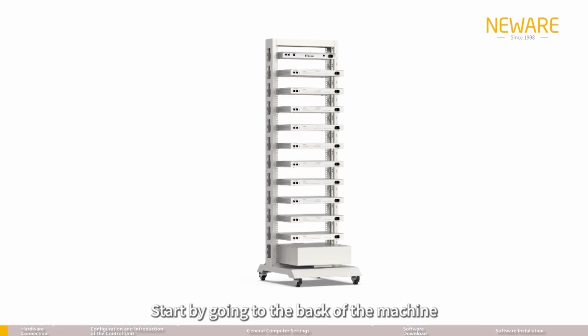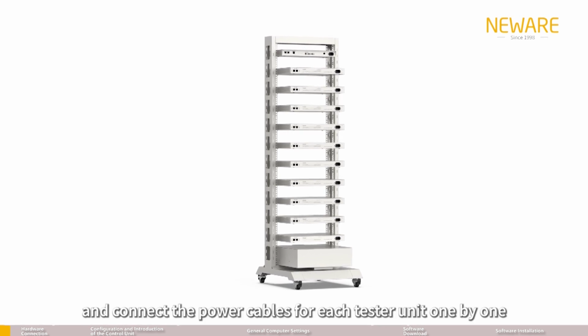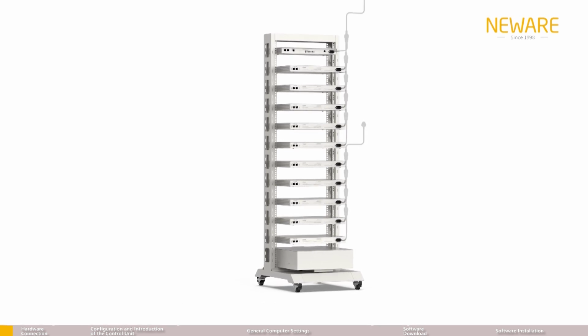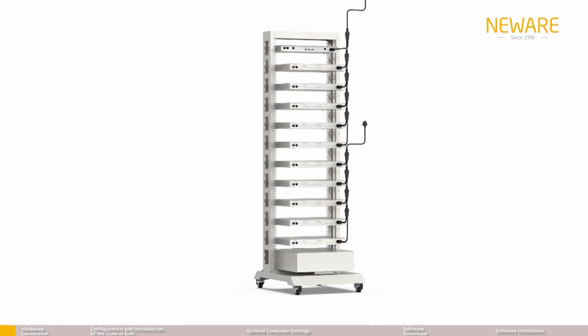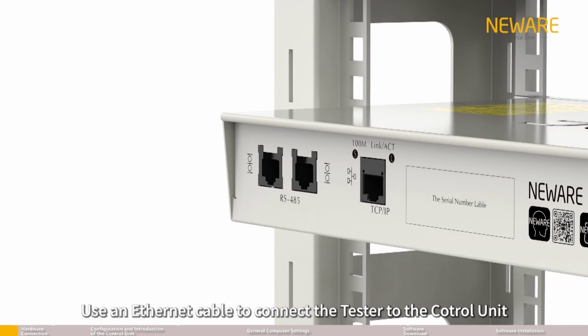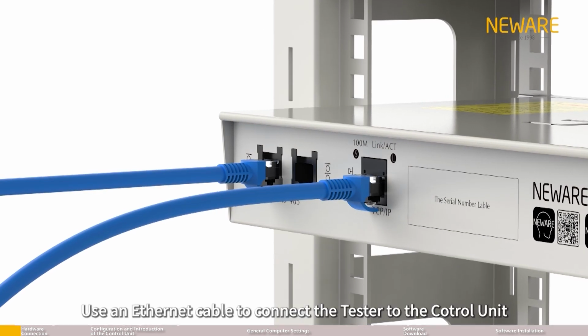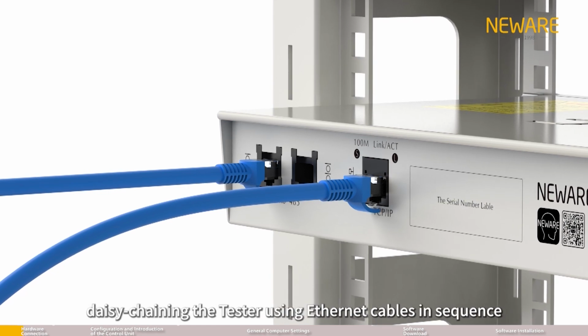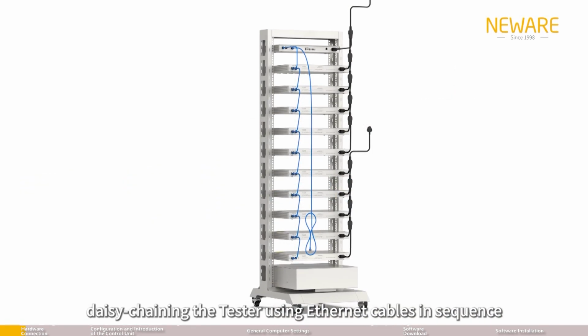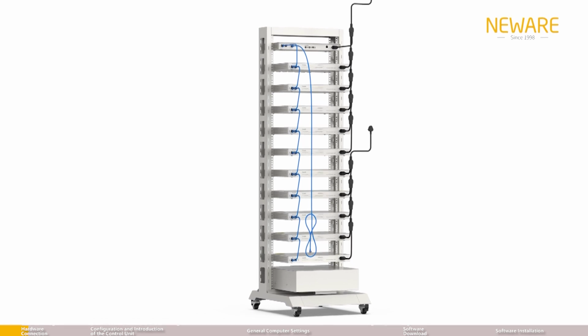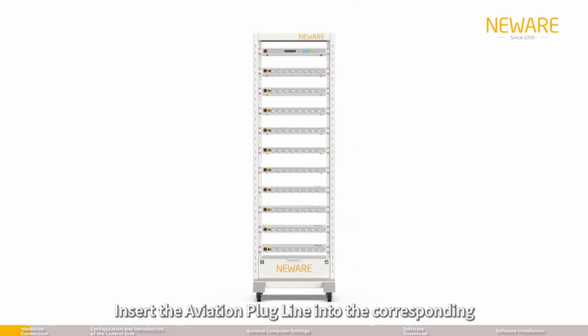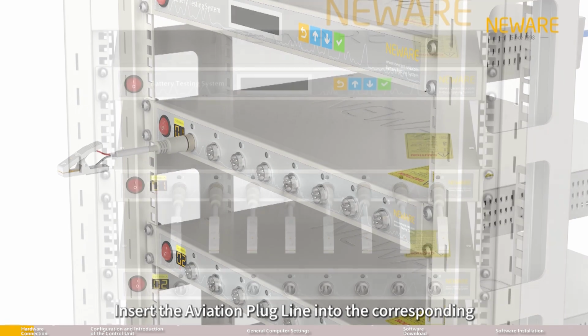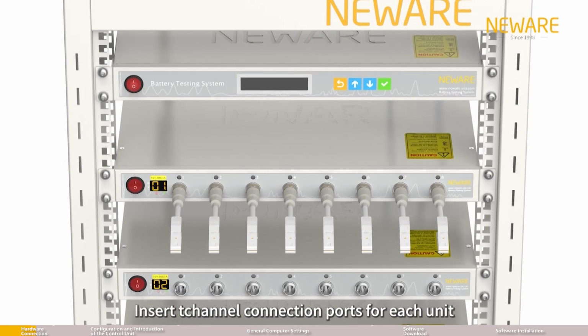Start by going to the back of the machine and connect the power cables for each tester unit one by one. Use an Ethernet cable to connect the tester to the control unit, daisy chaining the tester using Ethernet cables in sequence. Insert the aviation plug line into the corresponding channel connection ports for each unit.